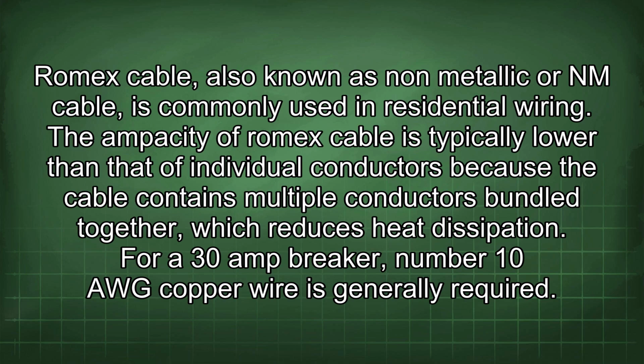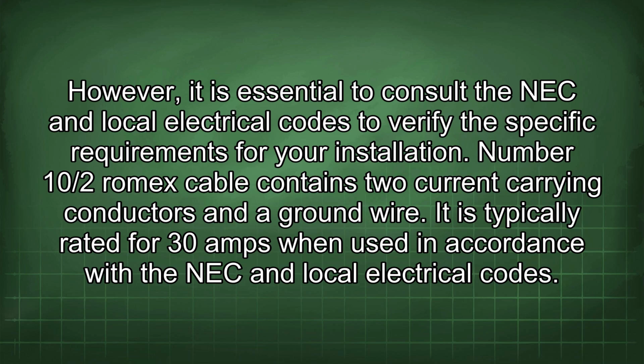For a 30 amp breaker, number 10 AWG copper wire is generally required. However, it is essential to consult the NEC and local electrical codes to verify the specific requirements for your installation. Number 10/2 Romex cable contains 2 current carrying conductors and a ground wire. It is typically rated for 30 amps when used in accordance with the NEC and local electrical codes.